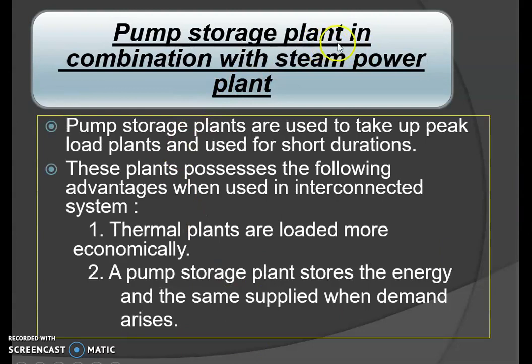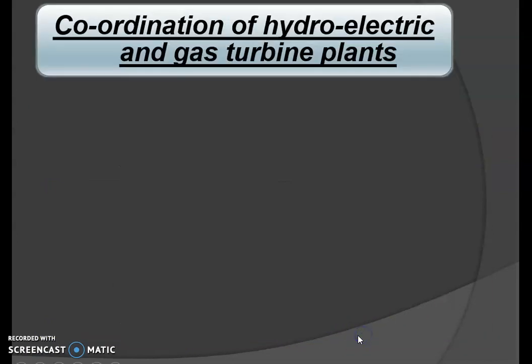Now the pumped storage plant in combination with the steam power plant. Pumped storage plants are used to take up the peak load and are used for short durations. These plants possess the following advantages when used in an interconnected system. Thermal plants are loaded more economically. Less load is imposed on the thermal power plant. A pumped storage plant stores the energy and supplies it when the demand arises.